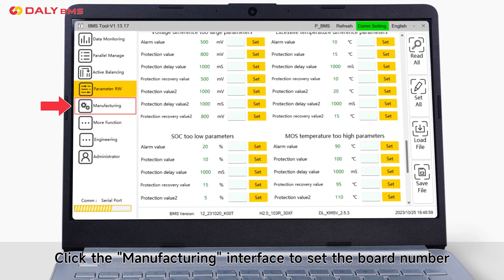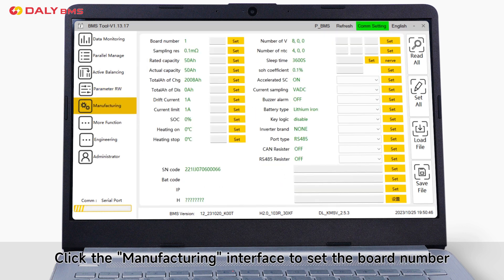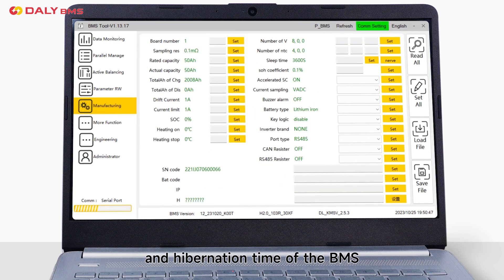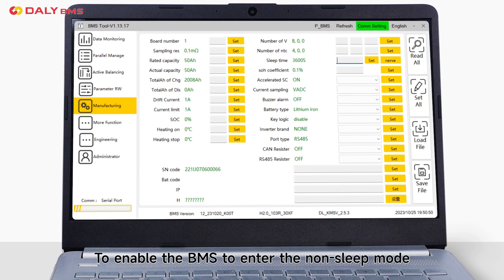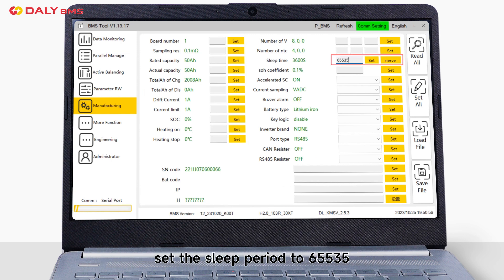Click manufacturing interface to set the board number and the hibernation time of the BMS. To enable the BMS to enter the non-sleep mode, set sleep period to 65535.